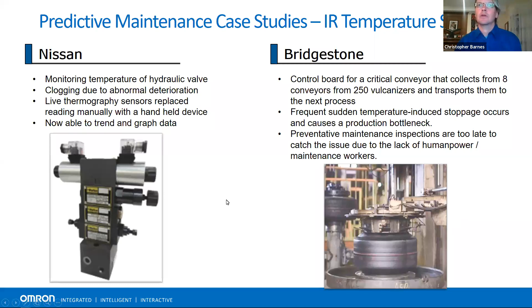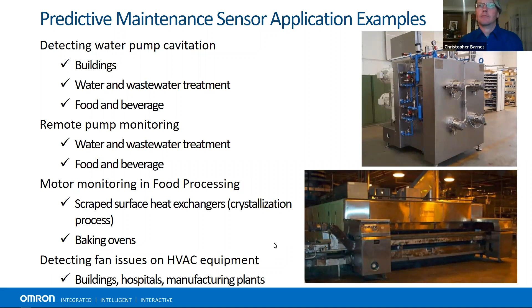Some other places they're useful: picking up water pumps, wastewater and water treatment, building, food and beverage. I mentioned before we've put them in quite a few hospitals now on critical equipment, everything from chiller plants to air handlers, cooling towers. And if you want to be really paranoid, like with the automotive example, they'll put all three of these rather than just picking one to put on a motor - vibration and temperature, insulation resistance, and current analysis - because they all pick up different symptoms, and sometimes depending on the failure mode, one will pick up the failure first.